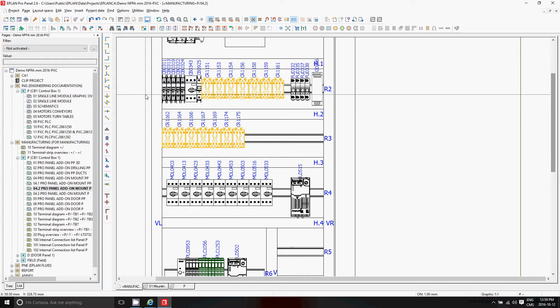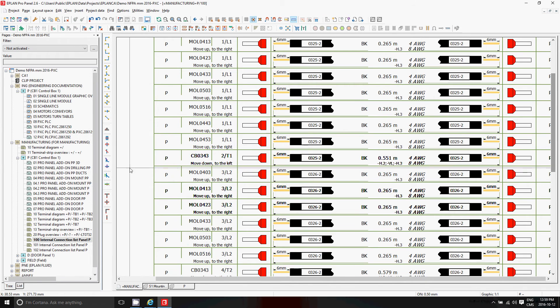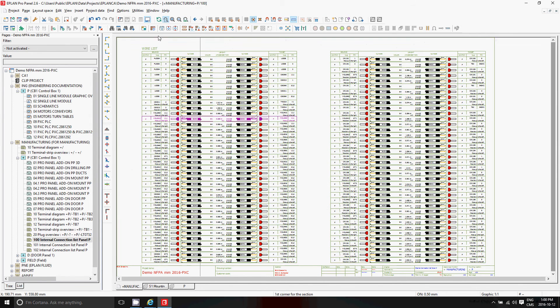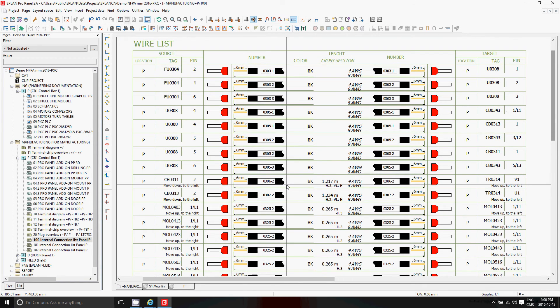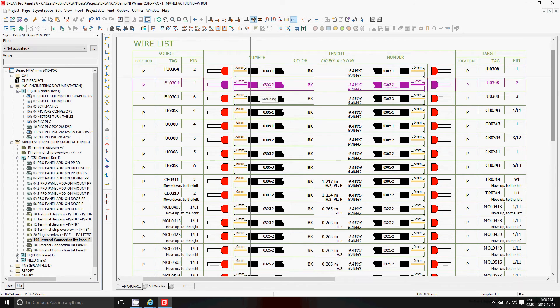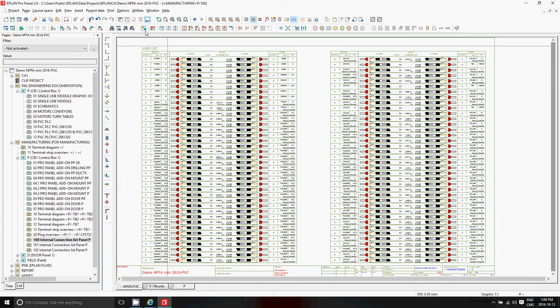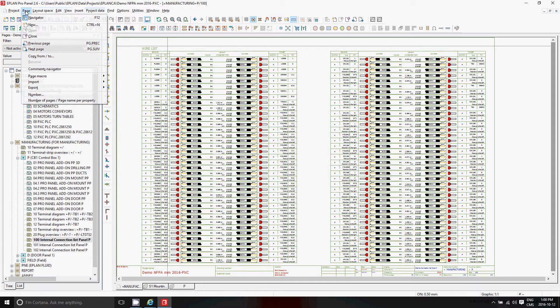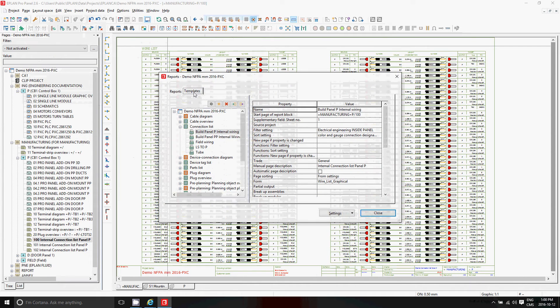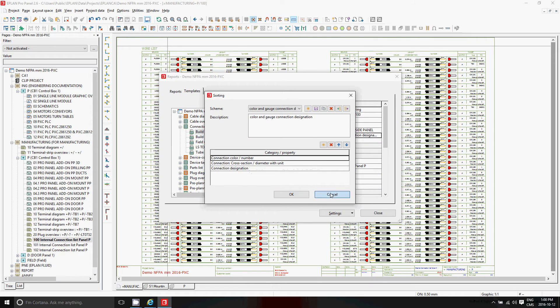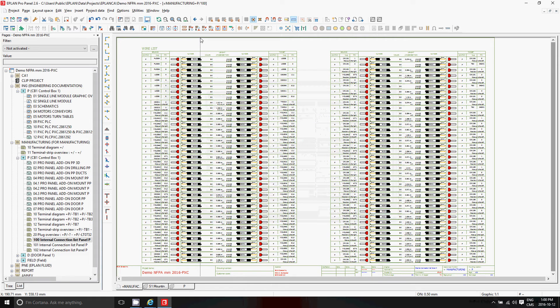And, typically, we would provide a user with a wire list. So, the wire list is a generated report that comes with a source and destination, and some details about the wire size, the length, the gauge, whatever. And it's all sorted in one specific way that was actually chosen during the report. When you are here in the generate report, you look at connection list, and inside the connection list, you can sort here by color, by gauges, or whatever. Now, of course, this may not exactly be suited to what the electrician wants.